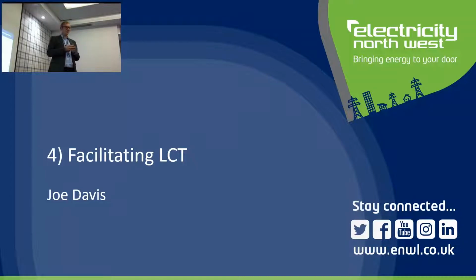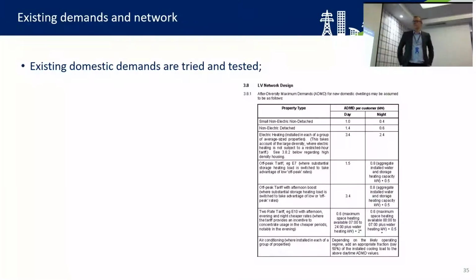This table here is one of our policy tables, what's known as an ADMD, after diversity maximum demand. I know you can't read it, but you'll have to believe me for a minute. These are all non-electric or gas heated properties where we use an ADMD of 1 for a non-detached property, and 1.4 for a detached one. That might be surprising because it's a very low figure.